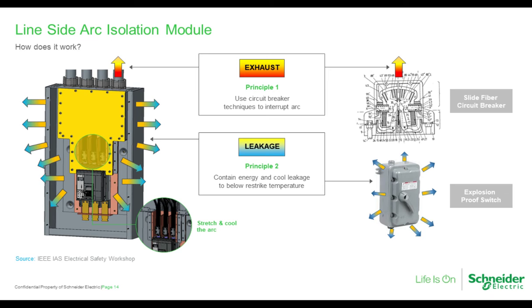As it turns out, our colleagues at Telemecanique many years ago had the same idea with what they called a slide fiber interrupter, which uses thermoset polyester barriers to control the arc as opposed to the more classic arc stacks. So even though we can interrupt the arc quickly, in less than 1 cycle, there's still energy in that 1 cycle inside the ArcBlok. On the circuits we're talking about, 480 volts, 100 kA, it's going to be on the order of 4 calories per centimeter squared. And we need to make sure that it stays separate from the user.